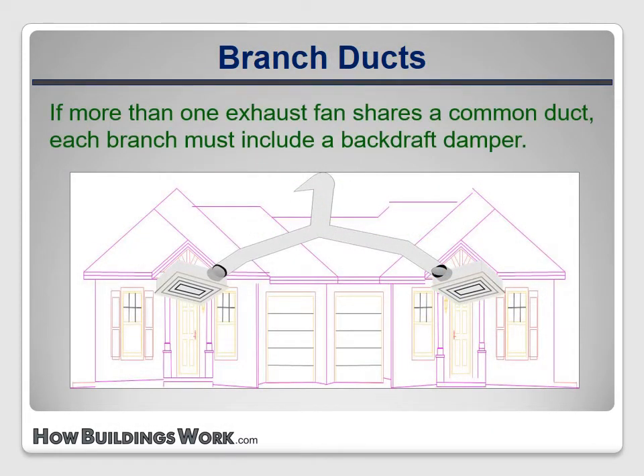If more than one exhaust fan shares a common duct, each fan must be equipped with its own backdraft damper to prevent cross-contamination. Most ceiling mount exhaust fans have one built in, but inline fans don't, so one must be installed in the duct in those cases.